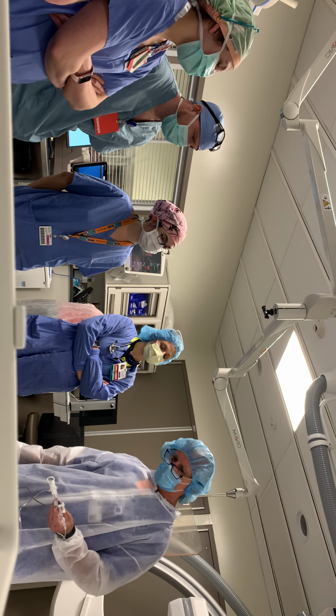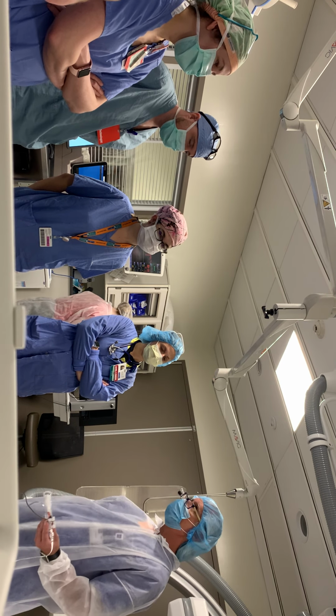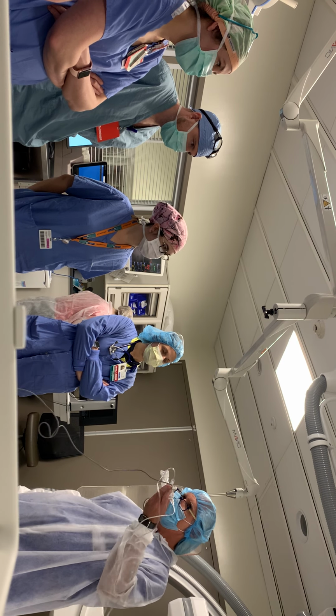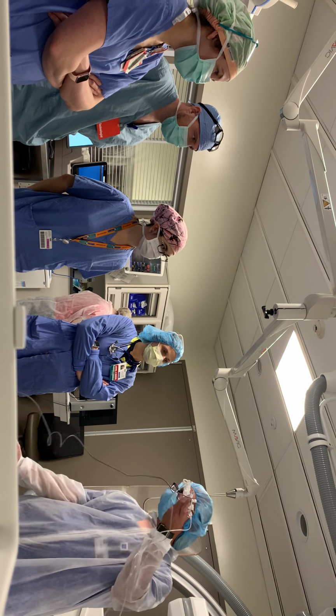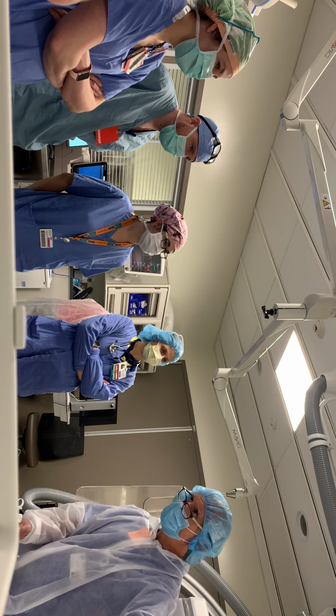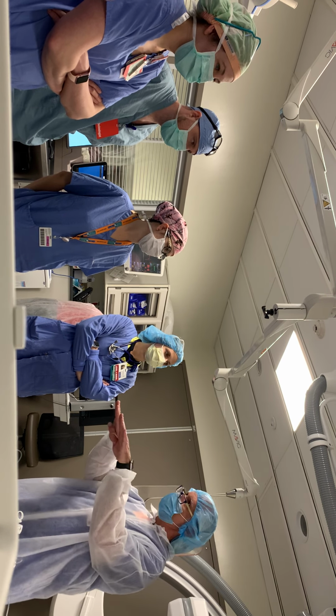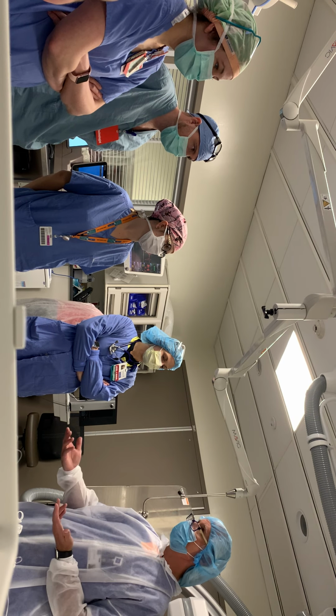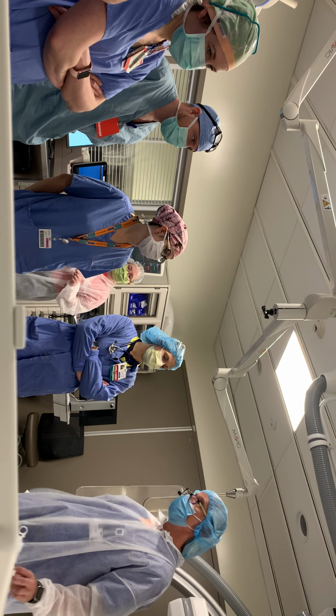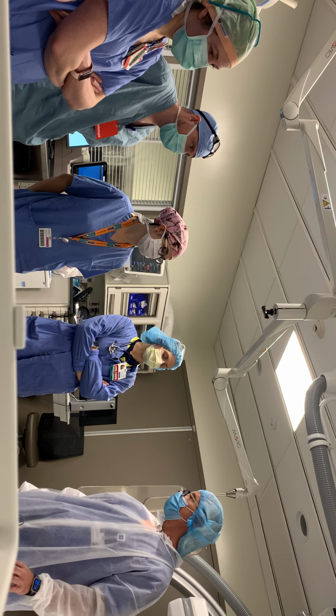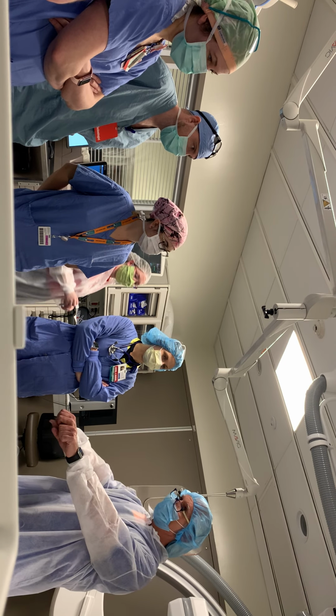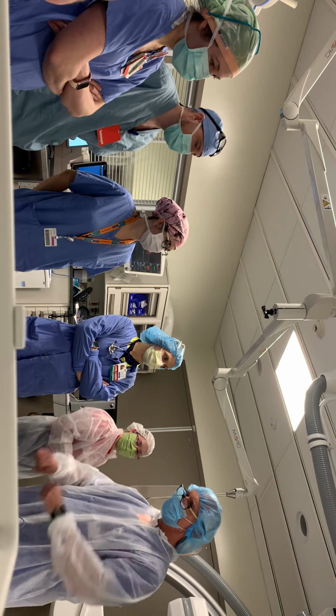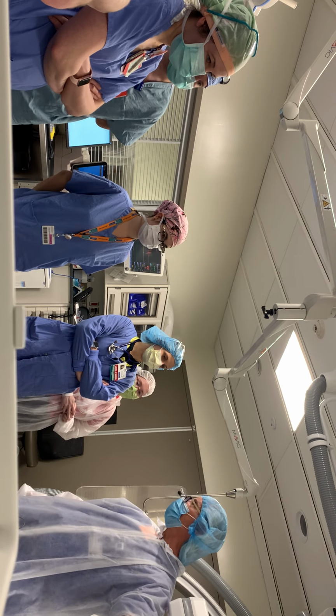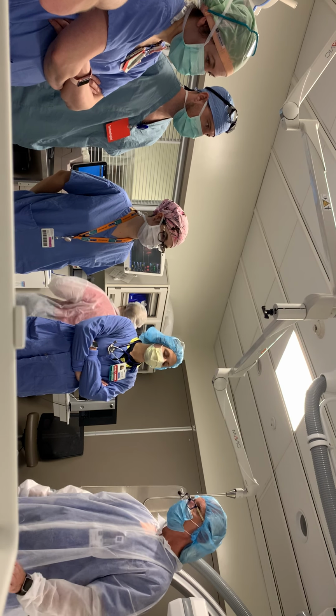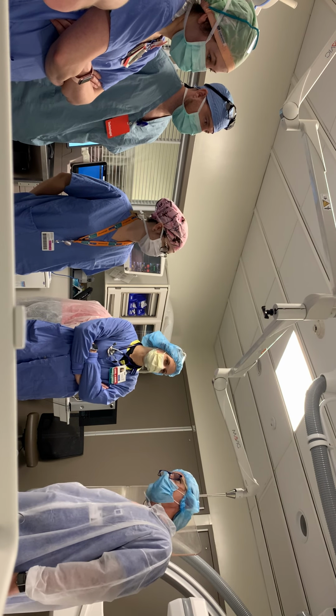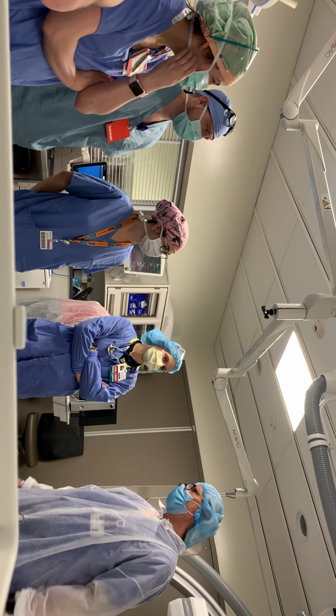Now when I'm on the pressure, unlike this system, it does not matter where my position is. I can have 2 of these at different positions. As long as that end is at the same position, we've fixed it. I think that that's actually a better system for you, especially because I'm told that you actually do use 2 of these on some of your cases. With the old system, they would have to be at the same physical position every time you took pressure measurement. This one, set it up, fix it once, and then this doesn't matter. You know, the chest, between the legs, it can fall off on the side of the patient, doesn't matter.